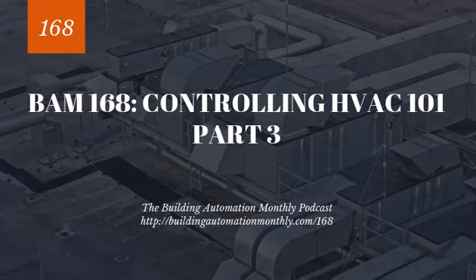Now, what goes on is you have the chiller, you have the chilled water side, you have the condenser water side, you have cooling towers, you have cooling tower fans, you have tower bypass valves, and you have heat trace. So all of these systems are being utilized to remove heat from the chiller through the use of evaporation at the cooling tower.